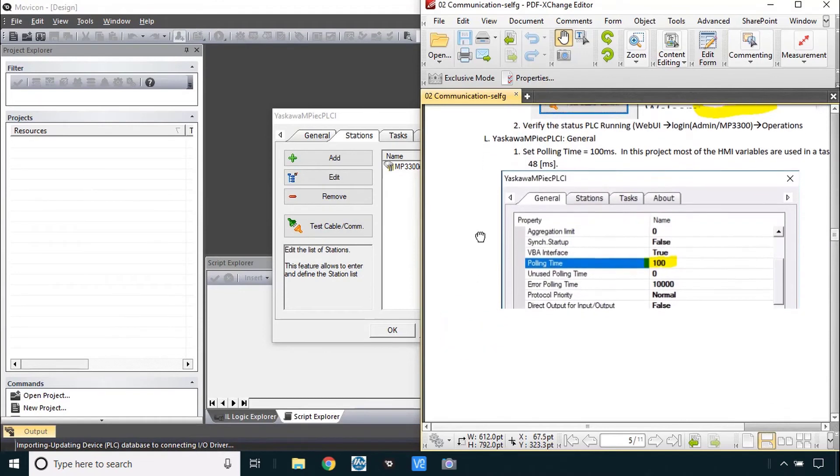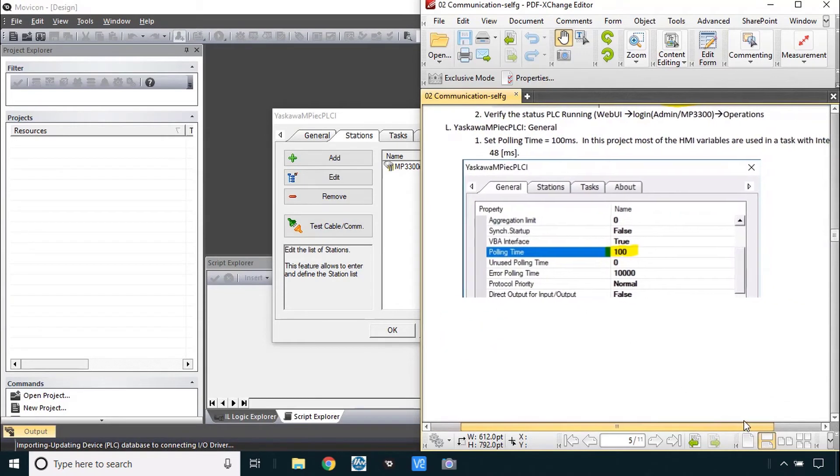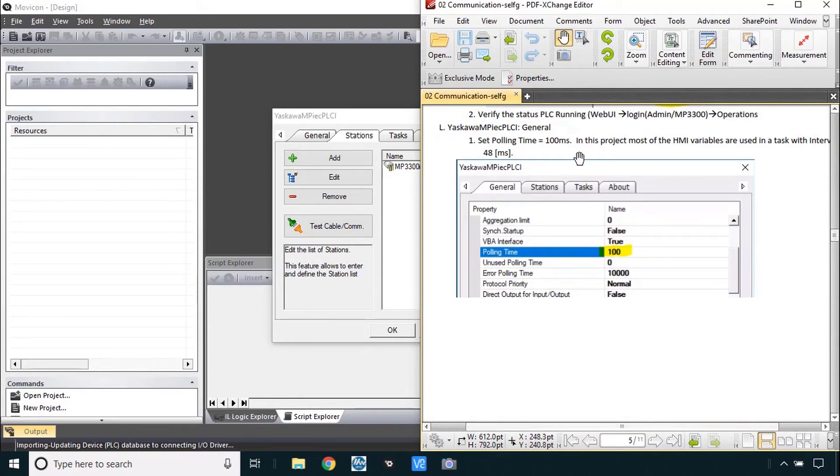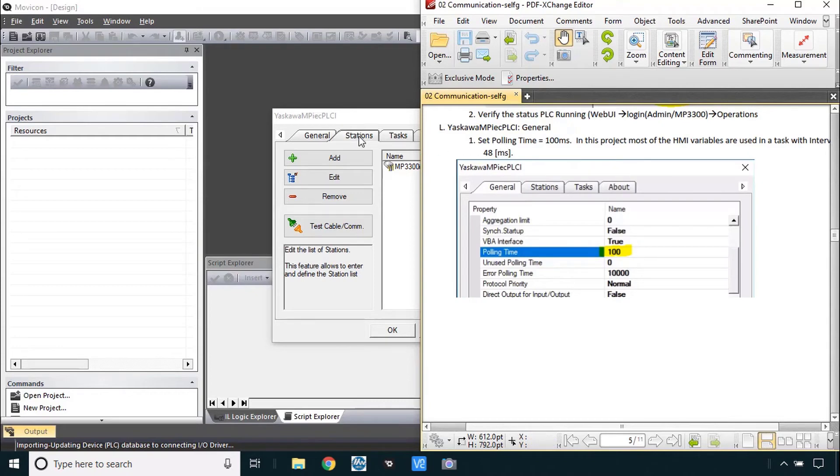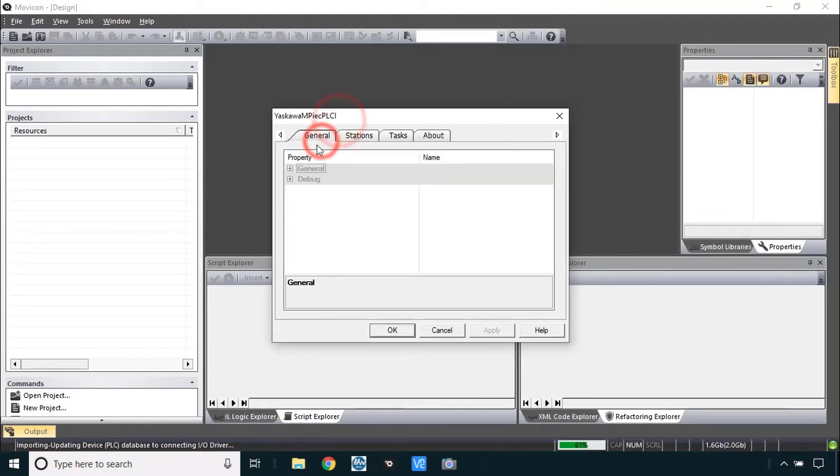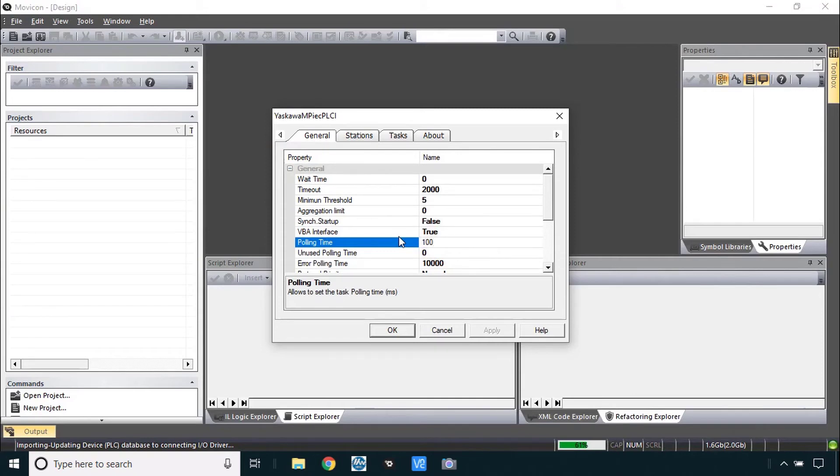Step L here this is a little bit different. We're having to set the polling time. As it says here most of the variables in this project in MotionWorks IEC are in a task running at 48 milliseconds. So if we set the polling time to 100 that means that every two scans of that PLC task there will be a possible update of the variables with this polling time. The idea here is you don't want to overload the communications with a polling time that's too low. 100 should be sufficient so we'll go here to the general tab and set that polling time to 100. OK.